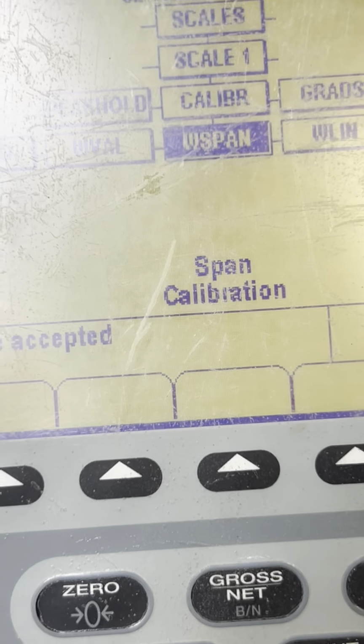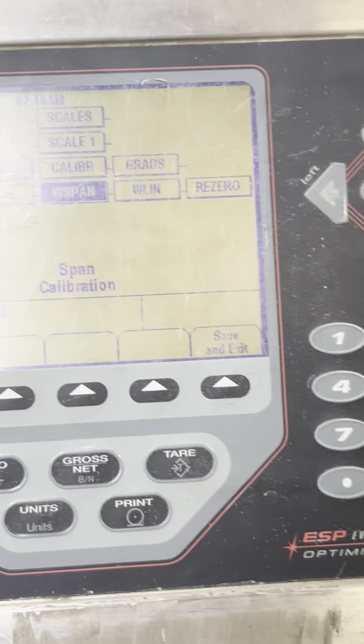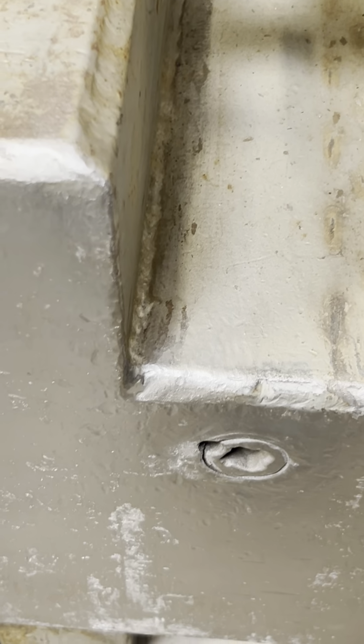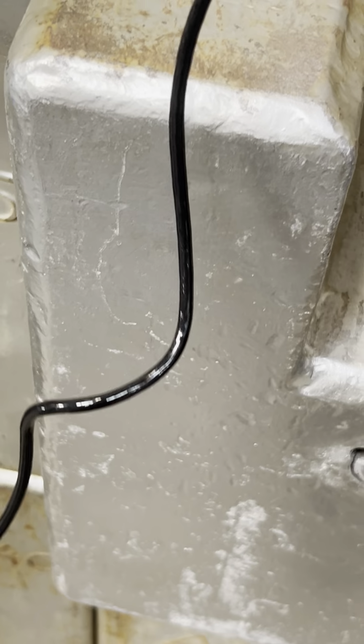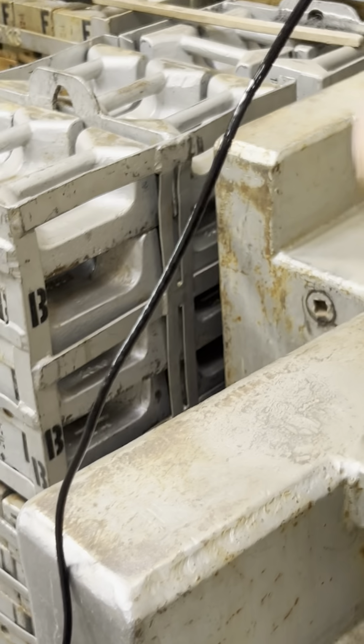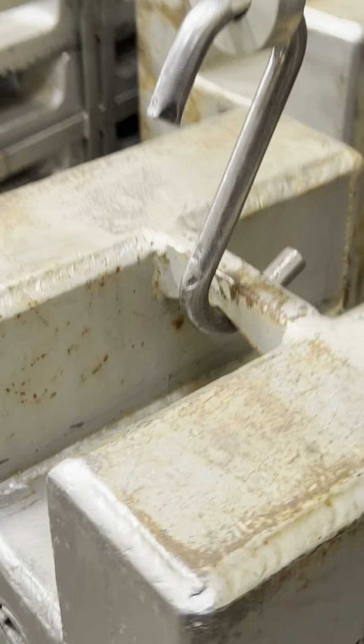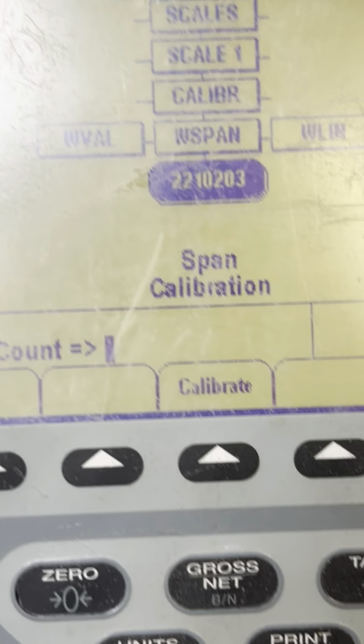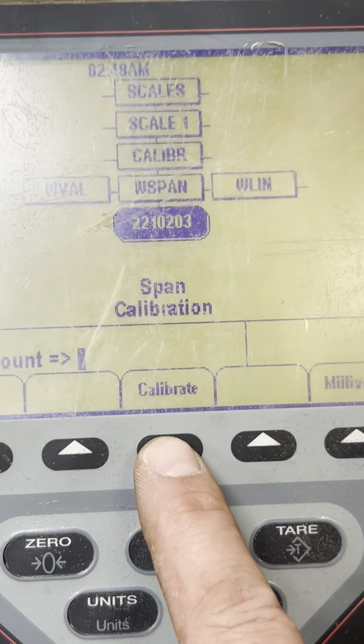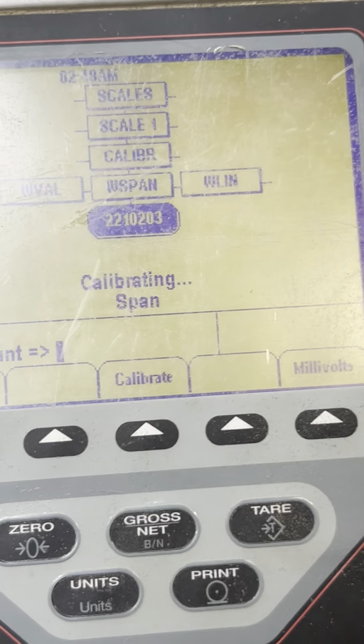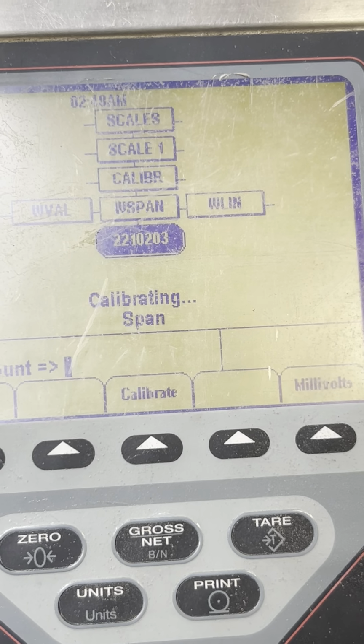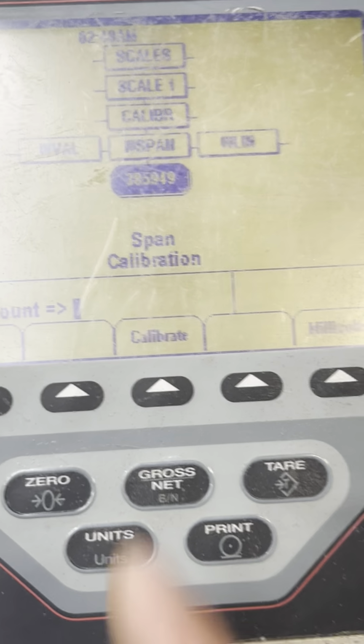Now it goes to span calibration. I press the enter button again, and now we will put the 500 kg weight. I put this 500 kgs on the load cell, and now we need to let it sit a little bit, like a couple of seconds, so it stabilizes. And when it's stabilized, we press the calibrate button again to calibrate with the weight. Calibration done.